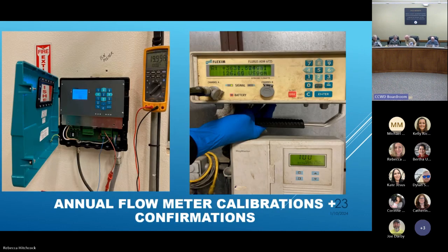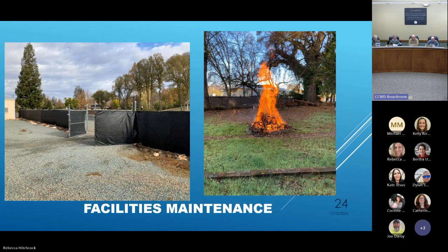That one question led into flow meter calibrations, where they test and calibrate flow meters. This is a calibration of the signal, checking that what the signal puts out matches verified flow. It's a 4 to 20 milliamp signal used for control and flow of a flow meter.